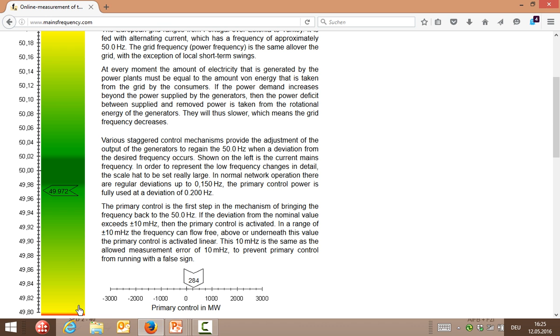There are 142 extra megawatt used to get the frequency up again. You see it works, it goes up slightly. This region here between 50 and 50.02 is not really a dangerous area, but if it goes beyond that, they have to do a bit more, and it must not go below 49.8 or above 50.2. If it goes outside those bounds, the system collapses.